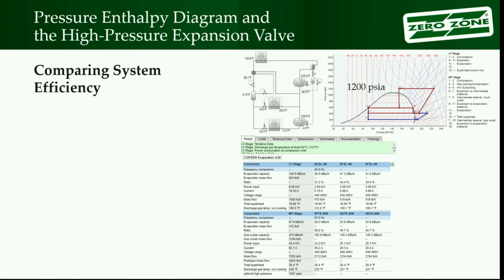I, however, know better because always when I've run into capacity issues on HFC systems, I always knew it was important to lower the head pressure, right? Things are warming up, it's a hot day, let's get that head pressure down and we will do more cooling. So I assume the person that put the controller together and did all that programming was dead wrong. Got it wrong. Somebody checked an invert box someplace in the software.